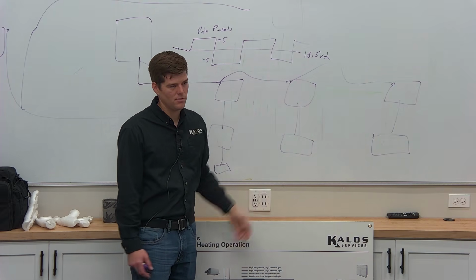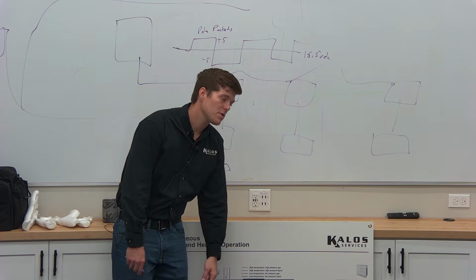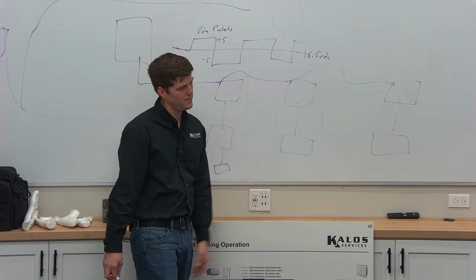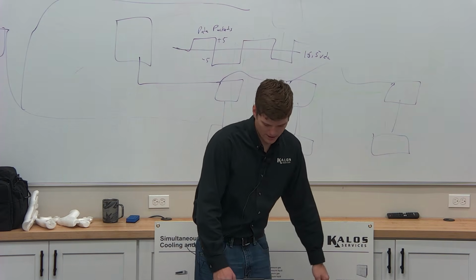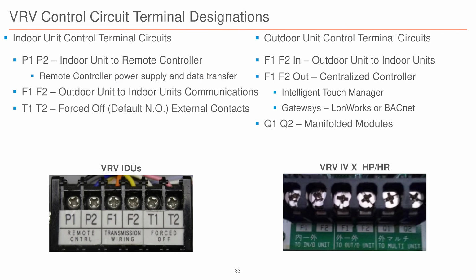Okay, there's a problem. The F1, F2 is the communication between all the indoor units, yeah. And that's both inside and outside. Correct, yeah. The outdoor unit's kind of shaded a little bit, and I got my trainer, I'll show you, but F1, F2 in on the outdoor unit, and then it's just the F1, F2. And so they're daisy chains.